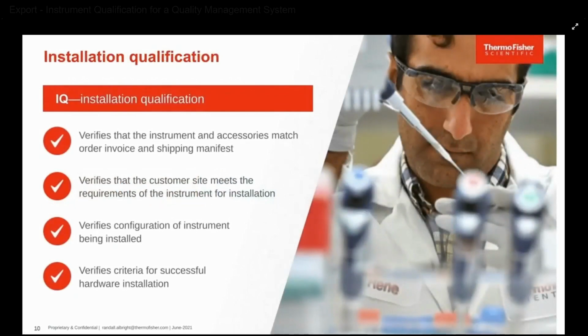The first component of the qualification is installation. By definition, the installation qualification will establish confidence that process equipment and ancillary systems are installed to the manufacturer's recommendations. Additional supporting details about installation instruction and test procedures can be found in section 820.170 installation. What does Thermo Scientific interpret this to mean for the instrument IQ? It means we will verify and document instrument or equipment against order invoices, any specific site requirements, any configuration details of the instrument or equipment, and specific install criteria. It should be noted that IQ or installation qualification is not repeated once the instrument or equipment is successfully installed. Follow-up qualifications would be called OQ-PQ.